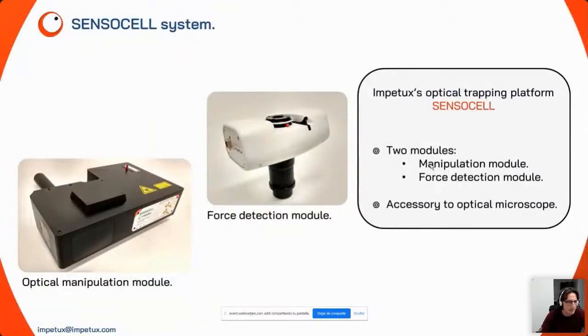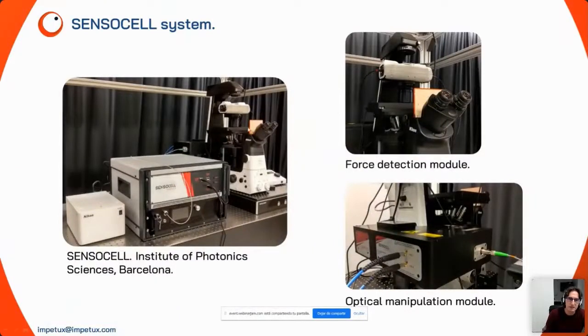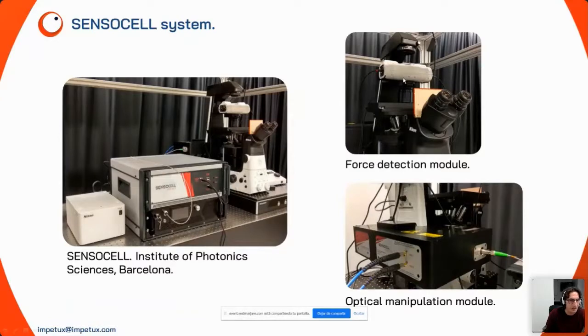The system is called SensoCell. It has two modules: the optical manipulation module, which generates the optical traps, and the force detection module. Both are accessories to an optical microscope. The force sensor, optical module, electronics, and laser are all visible in the complete system. The optical module attaches to the back port of the microscope via a laser fiber. The force detection module substitutes the condenser lens of the microscope but maintains imaging capabilities by letting light pass through.